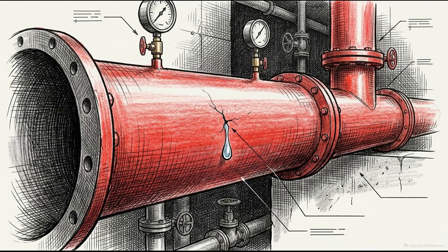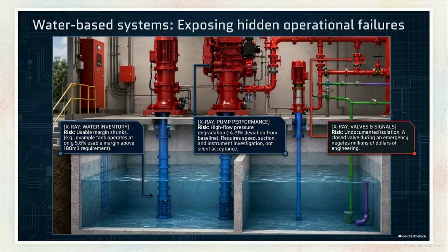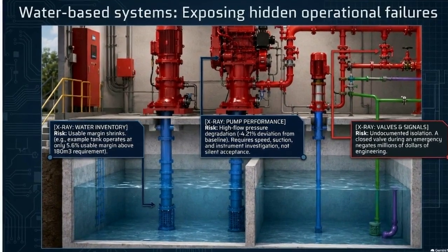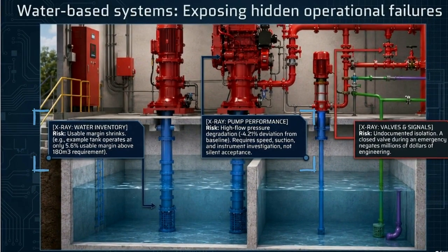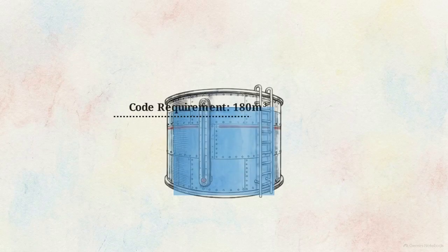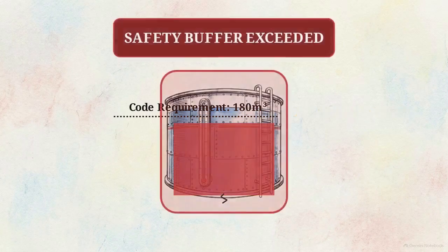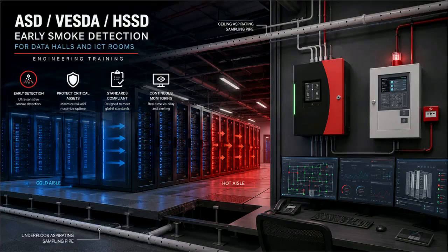Any maintenance act performed without this thread is a hidden failure, silently degrading the safety of the facility until revealed by a real event. This cross-section shows how technical governance exposes hidden degradation in water-based systems. It allows operators to monitor exact hydraulic performance and verify the volume of the water inventory. For instance, if a reserve tank operates with only a 5.6% margin above its code-required volume, any minor leak removes the facility's safety buffer. In high-density data halls, the focus moves to early warning systems, specifically air sampling detection, or ASD, which monitors the server aisles.